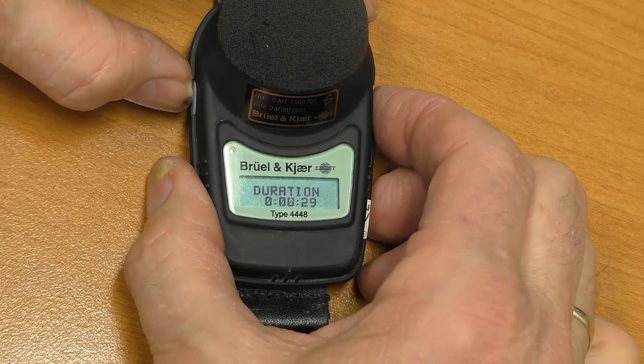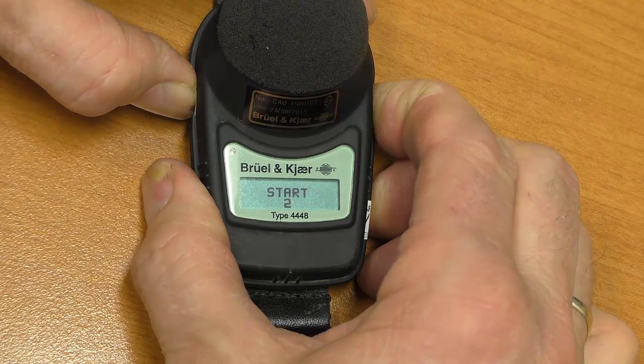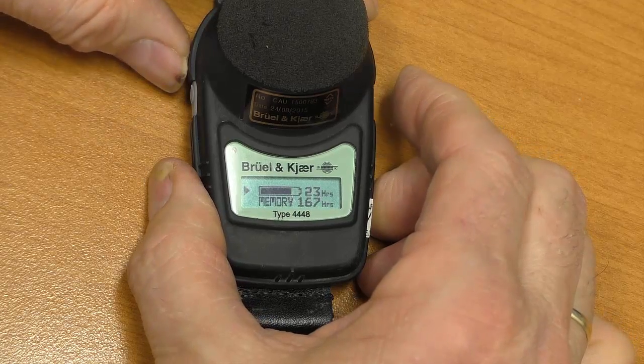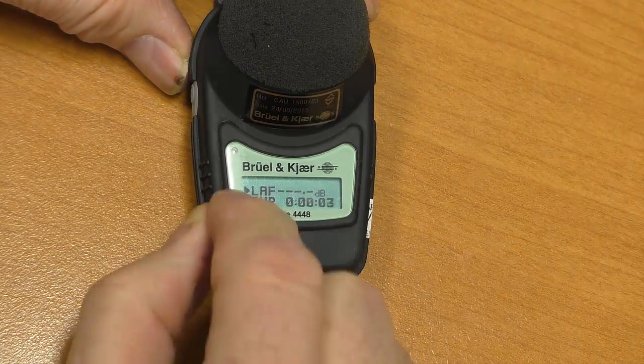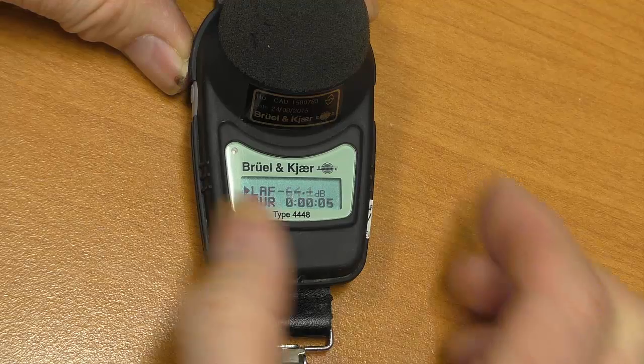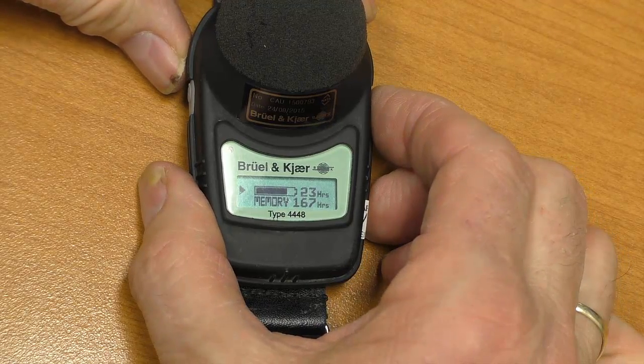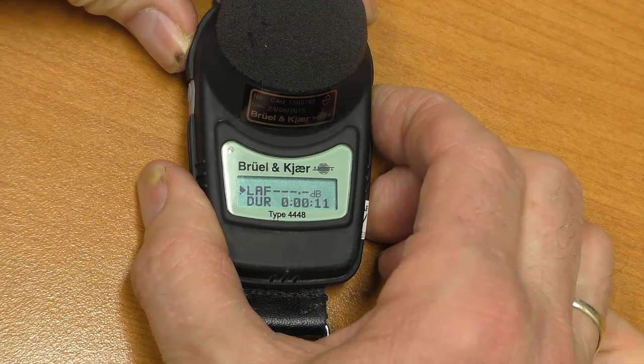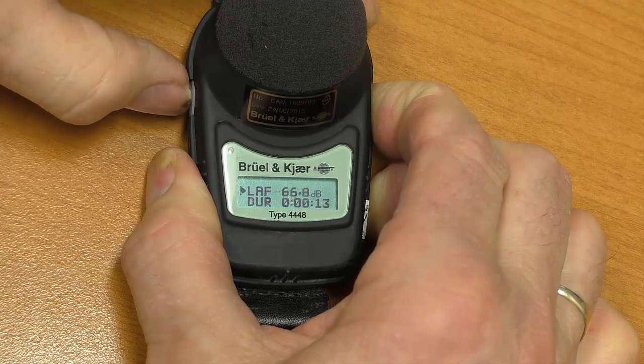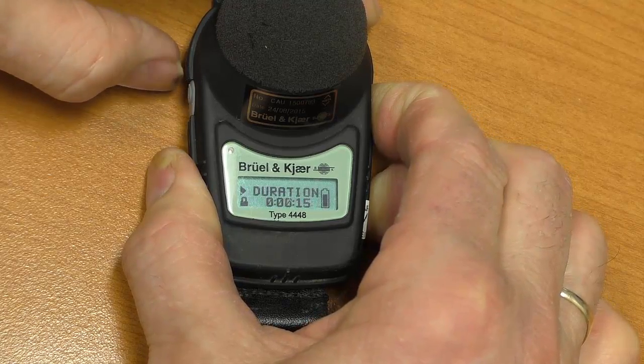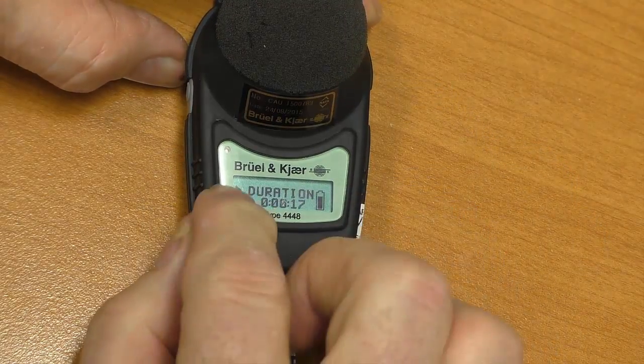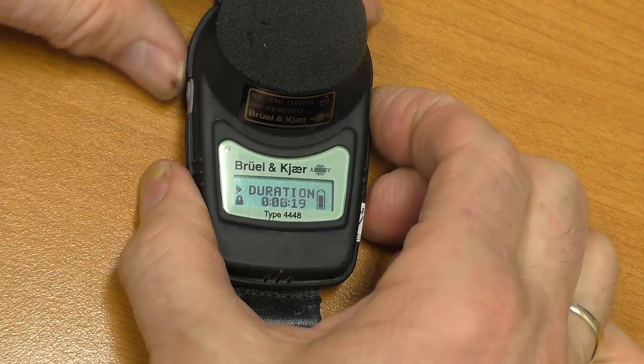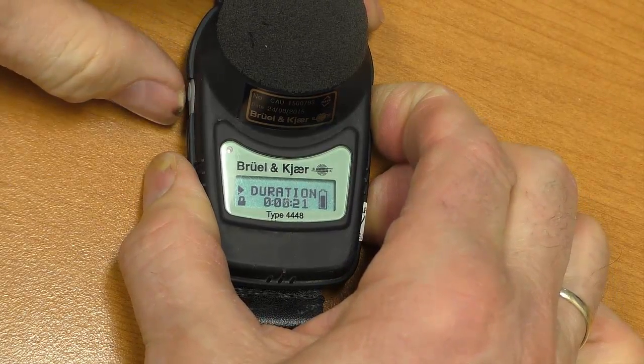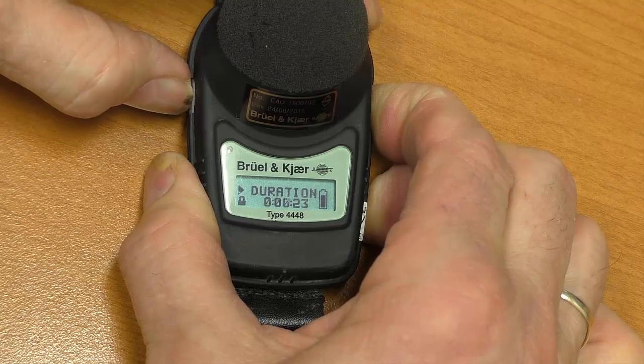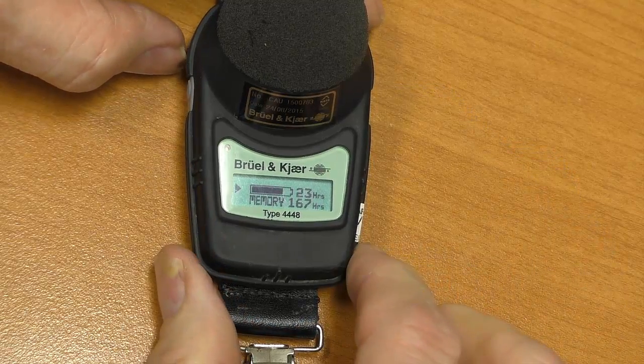We want to start logging, so we push both keys in. Here's our start symbol, it's now logging. You can see a little play symbol on the left hand side there. In order to lock the keyboard, we hold the right key in, then push the left key three times, and we've now locked the keyboard. It's playing. Now we want to unlock it. We hold the right key, push the left one, two, three, and we've unlocked it.